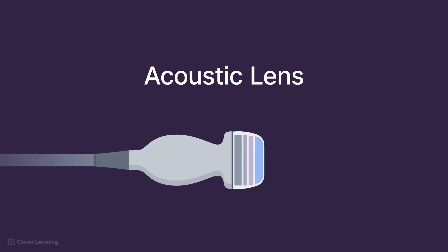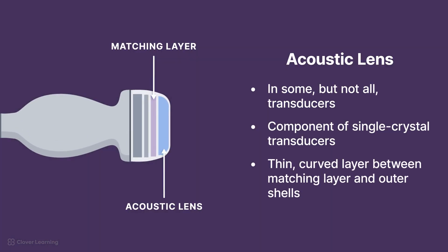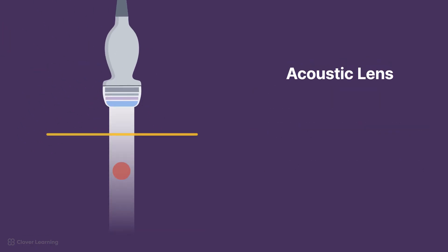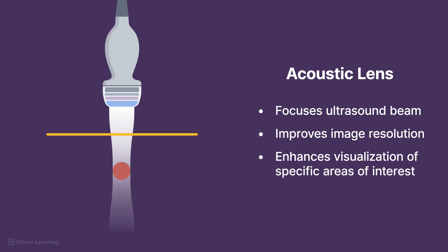Though not a component of all transducers, some single crystal transducers include an acoustic lens. The acoustic lens is a thin, curved layer of material placed between the matching layer and the outer shells of the transducer. Its primary purpose is to focus the ultrasound beam to improve image resolution and enhance visualization of specific areas of interest.